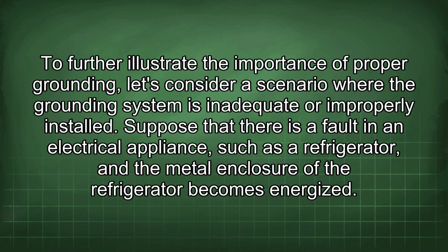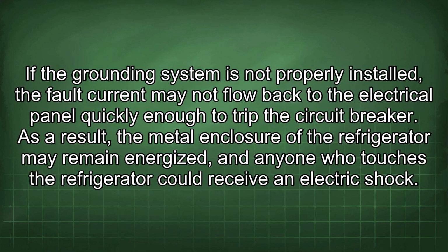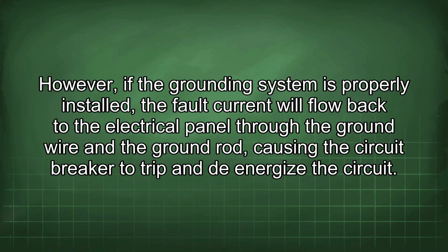To further illustrate the importance of proper grounding, let's consider a scenario where the grounding system is inadequate or improperly installed. Suppose that there is a fault in an electrical appliance such as a refrigerator, and the metal enclosure of the refrigerator becomes energized. If the grounding system is not properly installed, the fault current may not flow back to the electrical panel quickly enough to trip the circuit breaker. As a result, the metal enclosure of the refrigerator may remain energized, and anyone who touches the refrigerator could receive an electric shock. However, if the grounding system is properly installed, the fault current will flow back to the electrical panel through the ground wire and the ground rod, causing the circuit breaker to trip and de-energize the circuit.